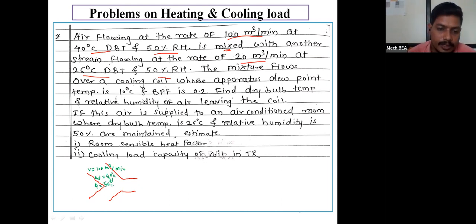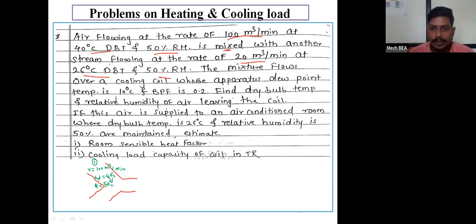Relative humidity is 50%. So here, if I consider this as point number 1, in that main stream we are mixing another air or another stream which has a volume flow rate of 20 meter cube per minute.